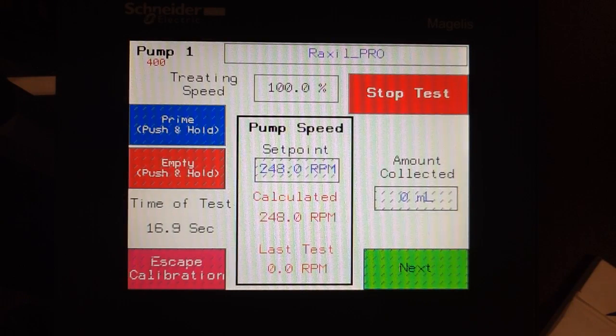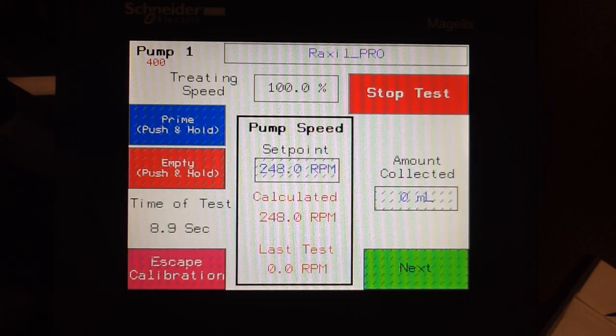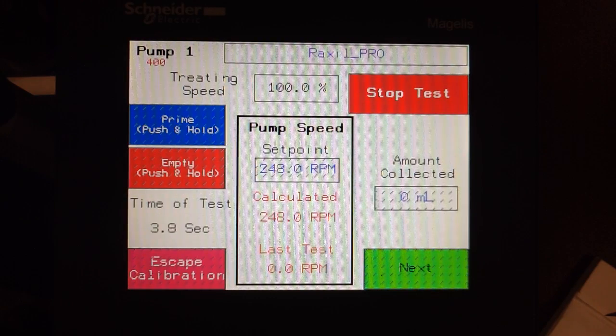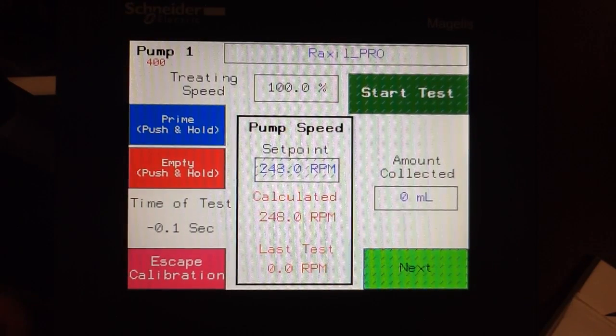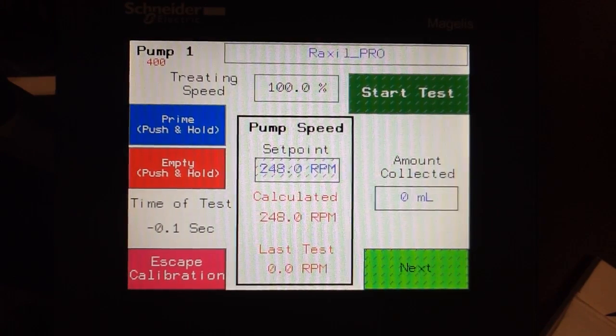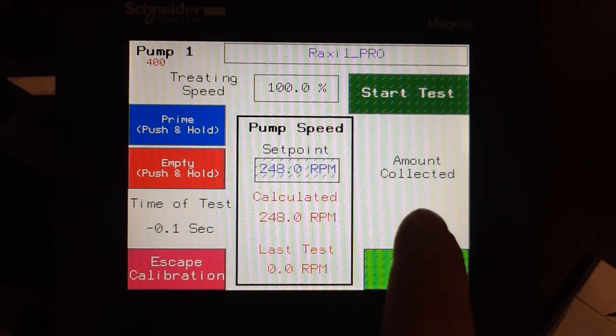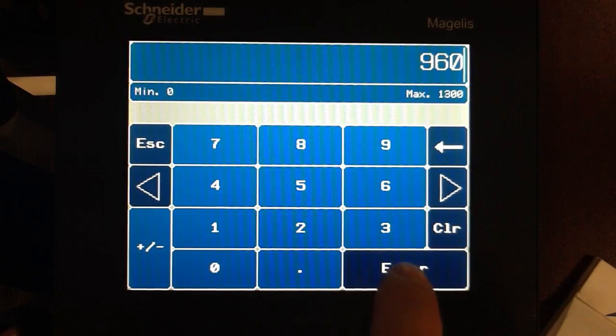During this test, it's going to run the last calculated RPM and the last time of test. If successful, we will collect 1000 mils. When the test is finished, enter the amount collected. If the viscosity has not changed, the amount collected should be 1000 mils. In this case, it has changed and we've collected 960 mils.